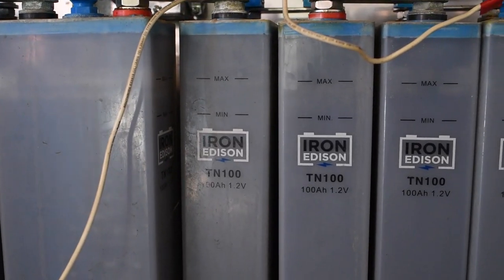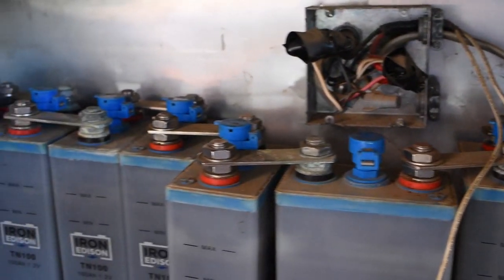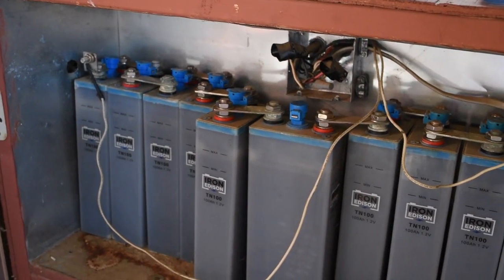The one thing you can't do with daylight drive is light up the lights at night, because there's no sunshine at night. So you do need batteries for lights. We run DC LEDs — they're quite efficient. We like nickel-iron batteries. It's important to recognize that what's popular for capitalist market-based economies is not necessarily what's best. This is a 12-year-old set of nickel-iron batteries — any other battery in 12 years would be dead. These batteries are just getting started; they're still running fine with no particular fatigue. Every seven or eight years you have to change out the electrolyte — distilled water and potassium hydroxide — it's not difficult and it's cheap. We have a 1946 nickel-iron battery that still works.